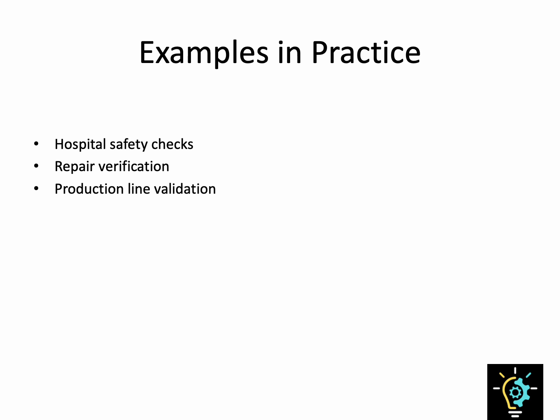So I want you to imagine a hospital running a safety check on infusion pumps every year. Under IEC 62353, the engineers would inspect each pump. They would run continuity and leakage tests, and then they would document the results. If a pump fails, it's taken out of service until repaired and tested. The same goes for ventilators or monitors after servicing. Before going back to a ward, they're tested against IEC 62353 to make sure they're safe.